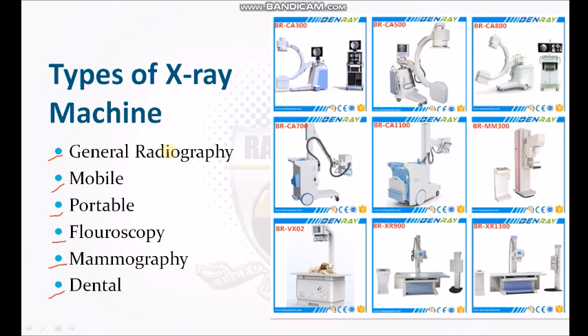And then they can be constructed as fixed, or they can be constructed as a mobile X-ray machine. When you say it is fixed, that means it remains in the room. Like for example, in RN, in MDC, those are fixed. We cannot bring them anywhere or remove them. And then it is also wall mounted, and some of the X-ray machines can actually be ceiling mounted. There are X-ray machines or facilities where the X-ray tube is ceiling mounted. Okay, and then for a mobile X-ray machine, like for example this one, all of them are actually mobile.